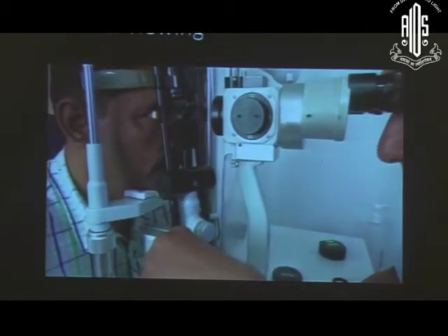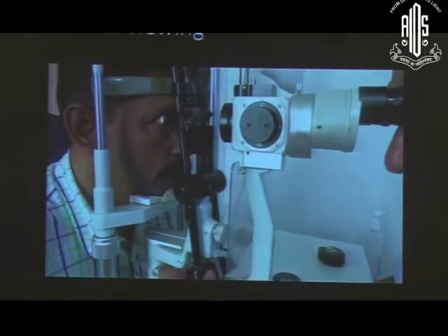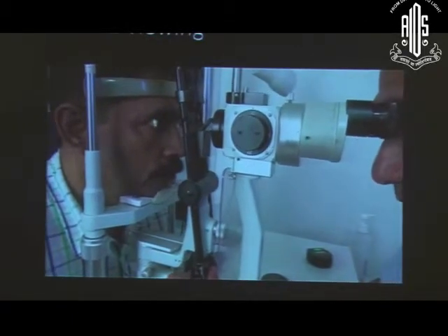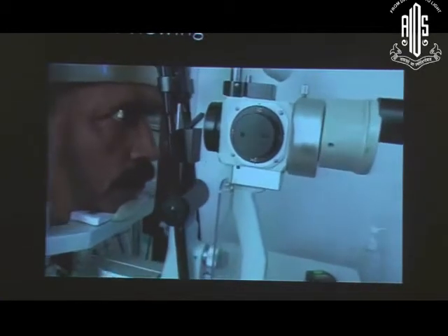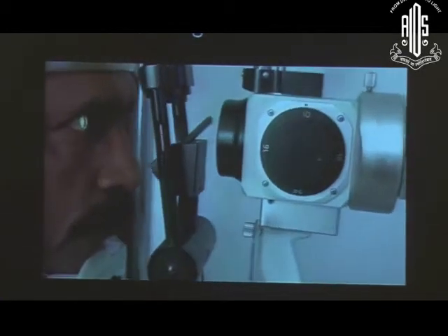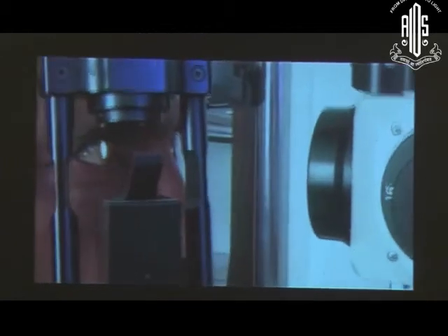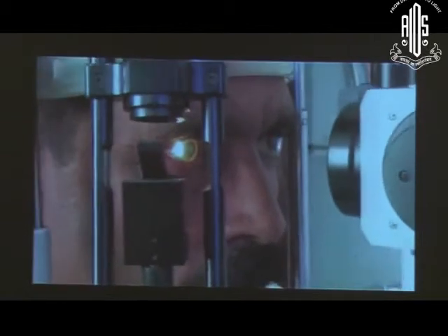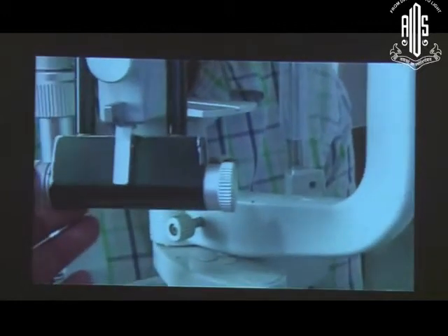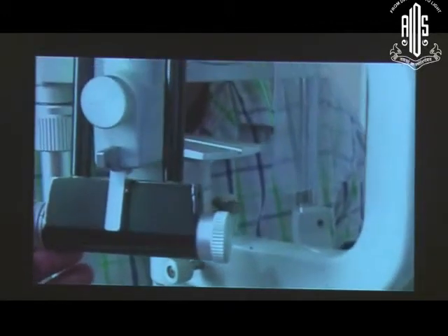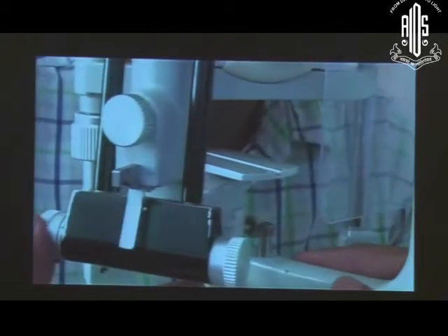Here retroillumination is done where you try to align the arm along the patient's visual axis and try to get a reflex from the fundus or from the iris if you're viewing anything ahead of the iris. Here comes sclerotic scatter, where light is thrown on the temporal aspect of the cornea so that the whole of the cornea lights up like a fiber optic cable, and you can see a golden glow around the sclera. So these are the two systems of illumination where you use non-parfocality.